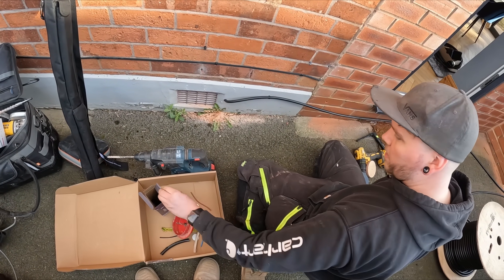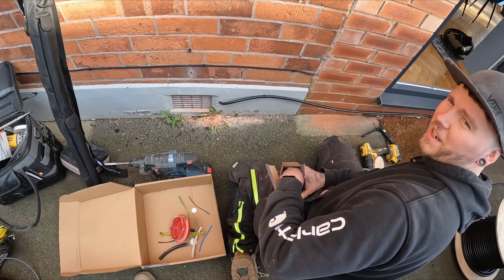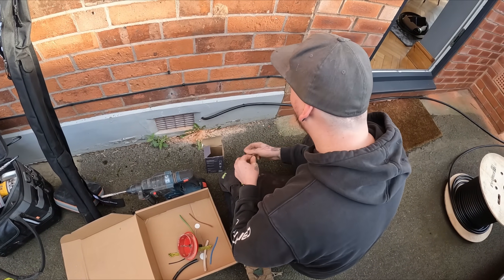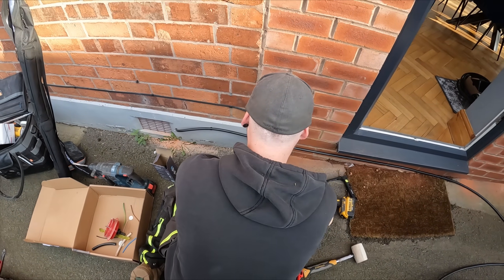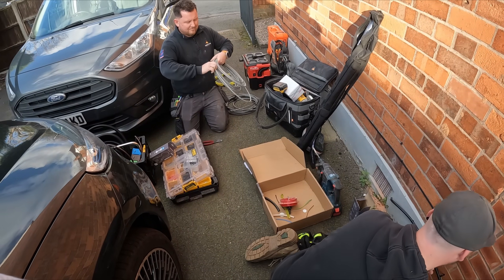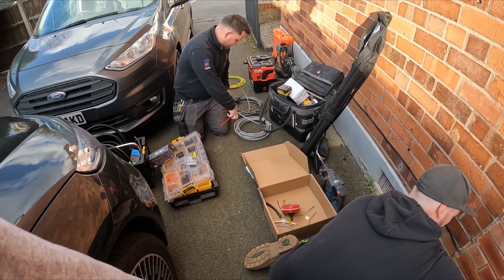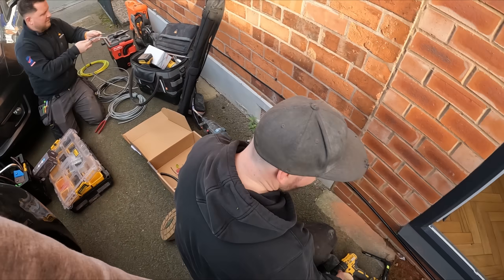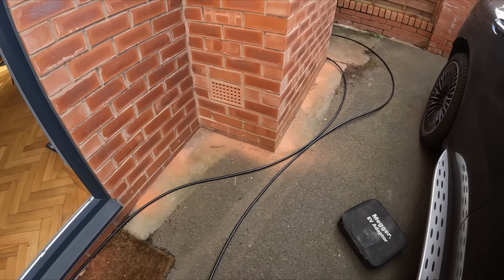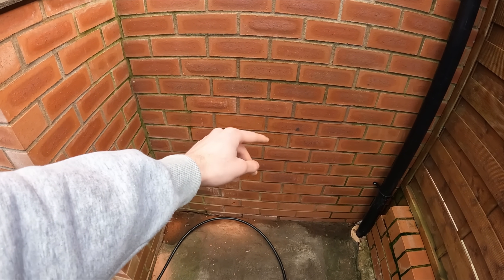That was a good job. Nick's come here to save the day - all the van's broken down so he's come out and we're on the job. We've been here half an hour and that side's all pretty much done. Mitch is prepping the board - 16mm tails, earth, Henley blocks. We're just clipping the cable all the way along, and then the charger's going down here, coming up into the EV box and straight into the charger.